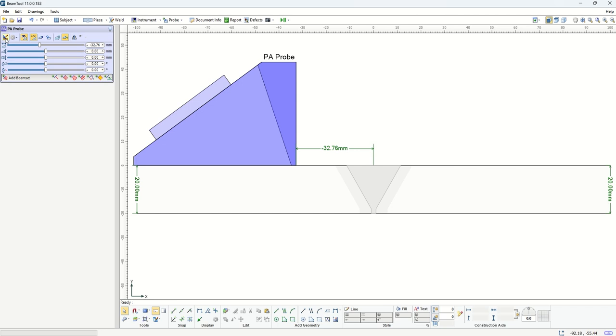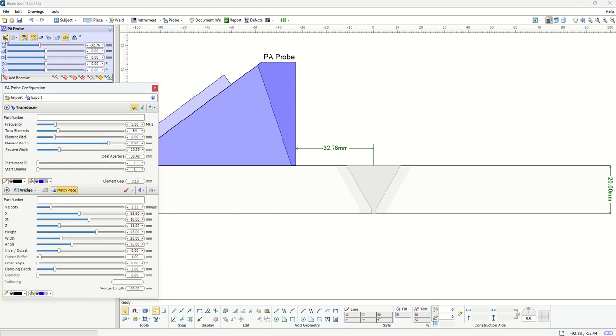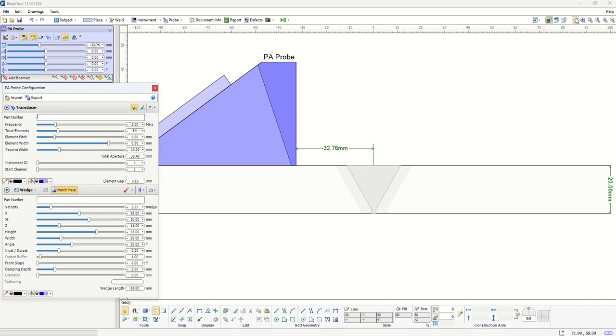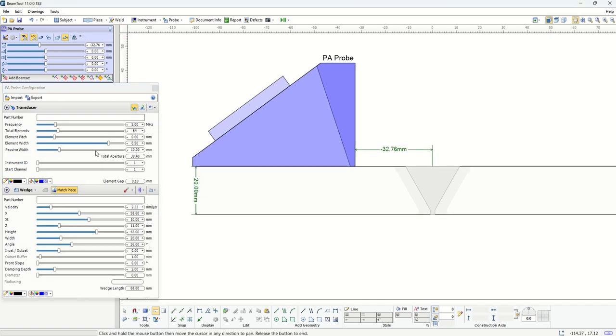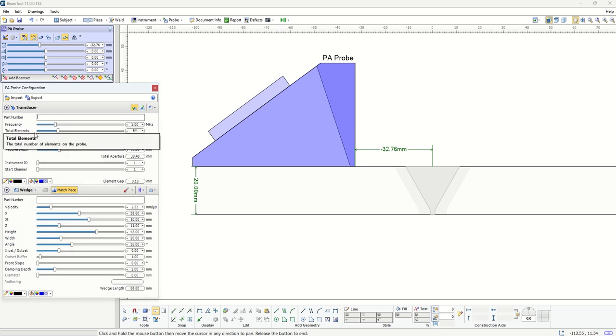When you click on this icon here, it gives us all the details of the probe and wedge which is already selected. As default, these are the parameters of the probe, for instance you can see its frequency, the total number of elements, pitch, and width.